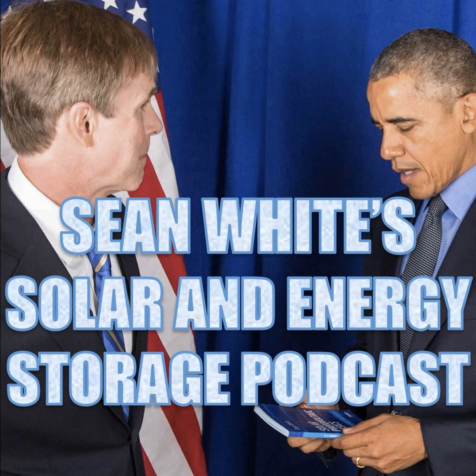705.13. And so this is where you can just add all kinds of stuff and use brains. So they call this PCS, or power control system. So you can just pretty much use CTs is what people are using to control the power output. One way of thinking of this is like, how often is somebody going to be blasting out all the power from their battery and all the power for their PV system at the same time? Probably never, because you're going to be charging your battery with your PV system instead of discharging your battery. Why not control all that stuff, and then you don't have to size everything based on the currents coming out of both at once, when you're never going to be putting them both out at once at the same time, because you can control it with electronics.